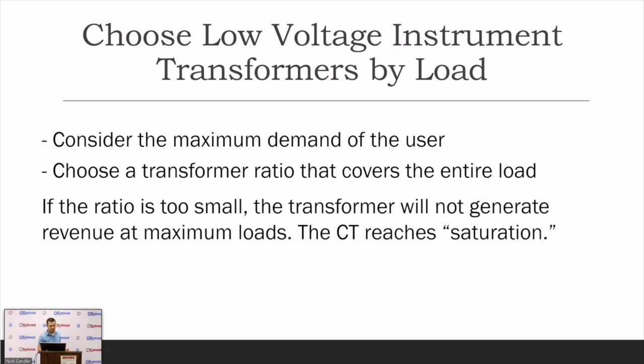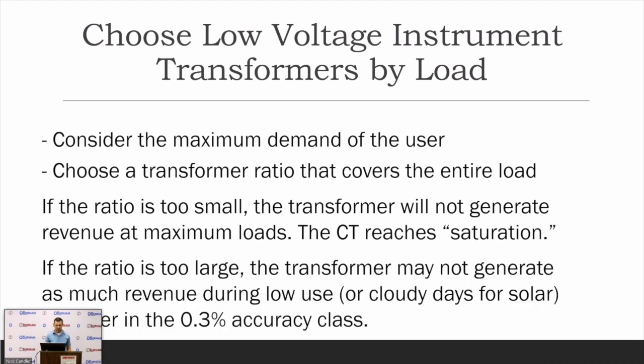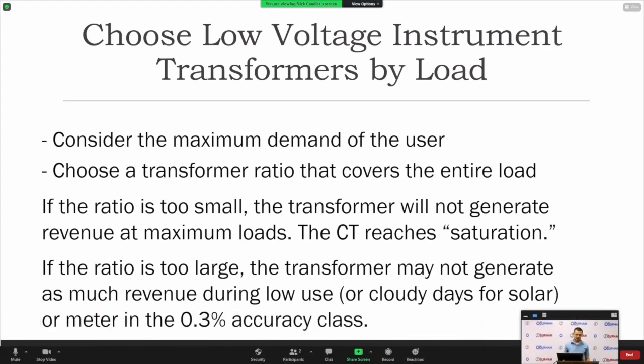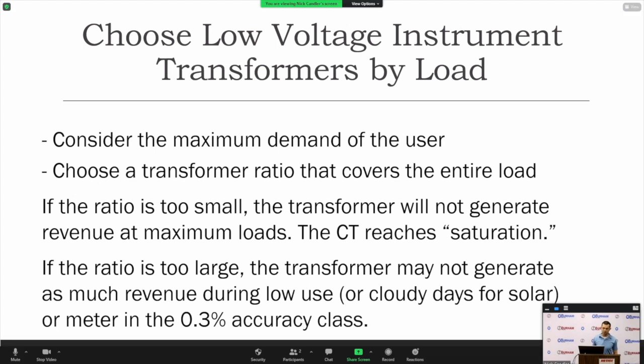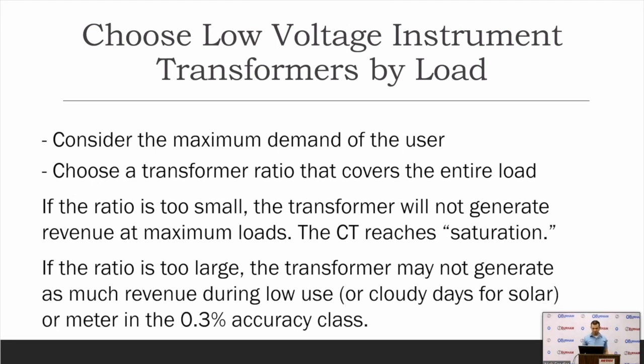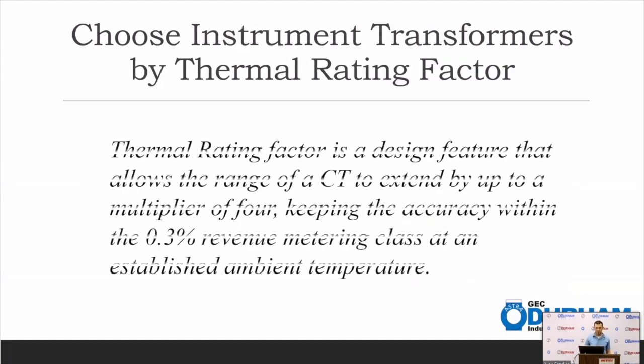But if the ratio is too small, the transformer will not generate revenue on maximum loads. The CT reaches what we call saturation. It's beyond its ability to perform and register at the meter. But if the ratio is too large, the transformer may not generate enough revenue down on the lower end. So this is especially true for solar installations. And for standard accuracy transformers, our goal is to stay in that ideal accuracy range. That would be 0.3 accuracy for both standard and extended range transformers.